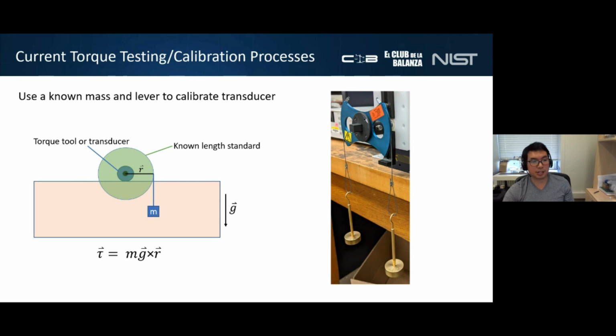So the second method is based off of the purest definition of torque, using literally sticks and stones by suspending a calibrated mass at the end of a calibrated lever arm. The image on the right shows a commercial torque wheel with commercial masses suspended from each side. This is common practice in calibration labs for calibrating small torque transducers and torque tools.